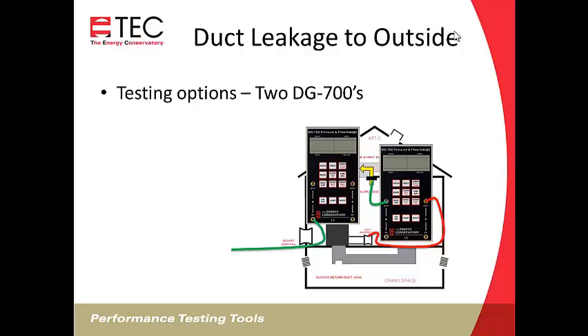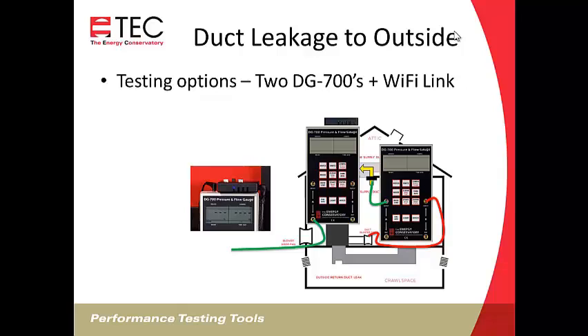The process is certainly much easier if you've got two DG700s. You'll set the first gauge to cruise 25. So as the duct blaster is turned on and changes the pressure in the house, your gauge will ramp it down and keep you at 25 pascals. And then with the duct blaster gauge, you'll bring the pressure to zero. So you'll increase the fan speed until you get to zero, and that's it. Then you'll document the test, and you're done.